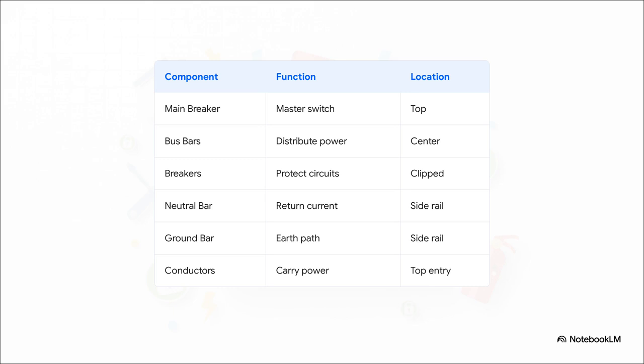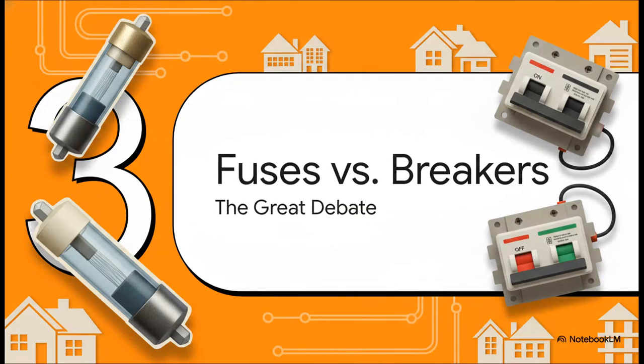But listen, I really want to draw your attention to the absolute danger zone here, the service entrance conductors. These are the massive wires bringing power from the meter to the main breaker. They are always live, always. Even if you flip that main breaker to the off position, those incoming wires will severely shock you. They must never, ever be handled by anyone other than a licensed professional. Section 3. Fuses versus circuit breakers.